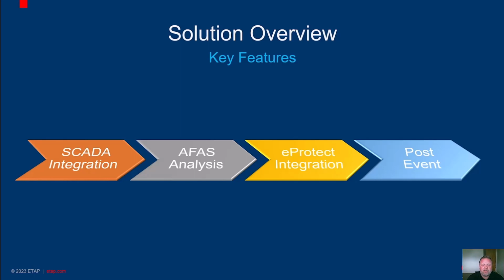The eProtect integration serves as the central repository of all relay asset information. Additionally, the calculation of the reach diagram and optimized distance protection settings can be determined using the eProtect solution, which is a valuable benefit to the AFAS solution. Lastly, the ETAP AFAS solution provides post-event analysis reporting that includes all details related to a fault incident, including the pre-fault, fault, and post-fault conditions, executed relay protection schemes, affected areas, relevant calculations such as fault location, fault type, fault current, fault voltage, and much more.